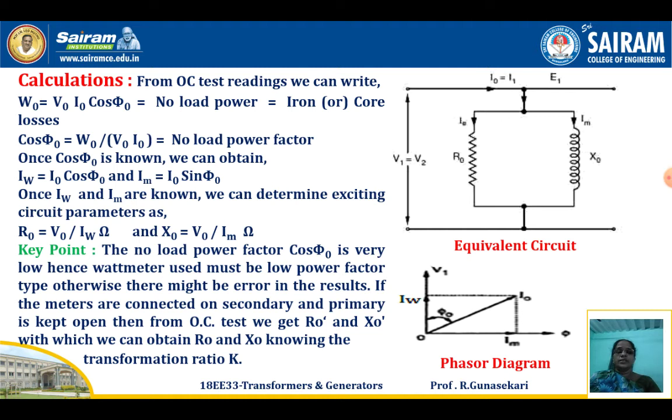In this case, the no load power factor cos φ0 is very low. Hence, a low power factor wattmeter is used in the OC test for measuring the no load power.